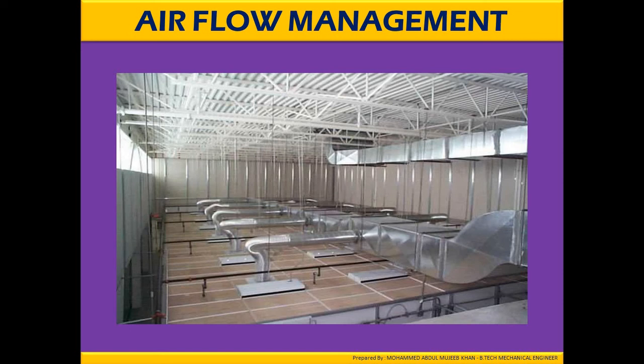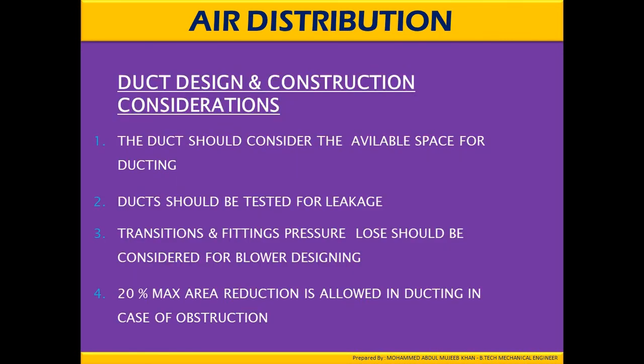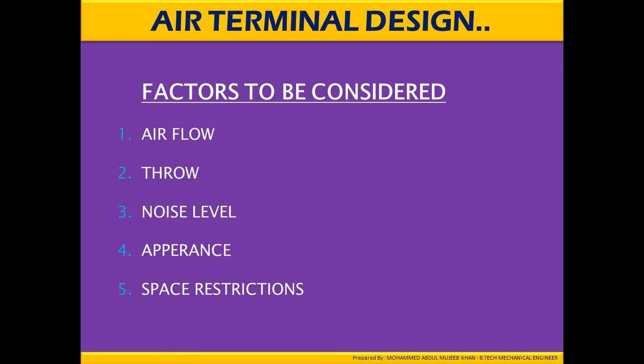Airflow management and duct design construction considerations: the available space for ducting must be considered. Ducts should be tested for leakage. Transition and fitting pressure losses should be considered for blower design. A maximum 20% area reduction is allowed in ducting in case of obstructions. Factors to be considered include airflow, throw, noise level, appearance, and space restrictions.